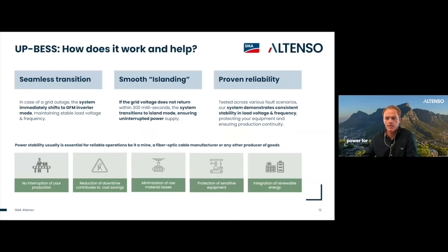So just to provide an overview, in the event of a grid disturbance event, the grid forming inverters would step in with support of the decoupling choke, and it would maintain the load voltage within a stable tolerance band without the system tripping. So we've done extensive tests, and the solution, regardless of whether it's a 3-phase, 2-phase, or single-phase fault, the system's very robust and is able to handle all fault scenarios.